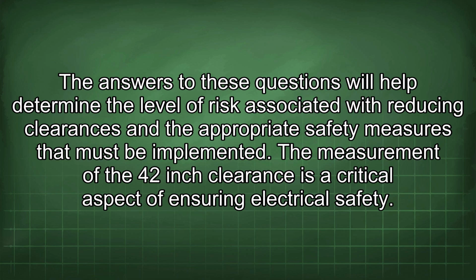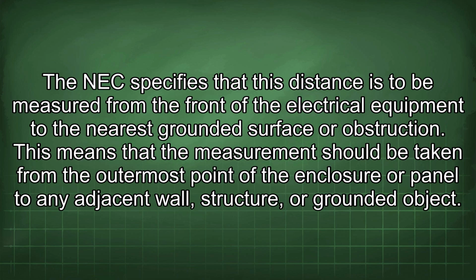The measurement of the 42-inch clearance is a critical aspect of ensuring electrical safety. The NEC specifies that this distance is to be measured from the front of the electrical equipment to the nearest grounded surface or obstruction. This means that the measurement should be taken from the outermost point of the enclosure or panel to any adjacent wall, structure, or grounded object.